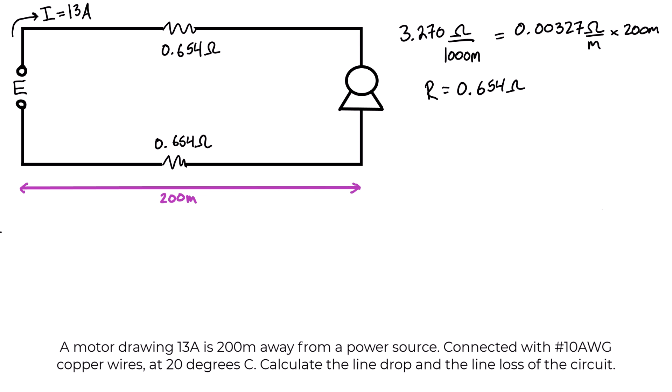If you're not given this number 3.270 ohms per thousand meters, you might be given other table values or expected to know other table values. The alternative way to get to this answer would be to know this equation where resistance equals resistivity times the length of the conductor divided by the cross-sectional area. Maybe this formula looks familiar, or maybe some of these values have been provided, or you're expected to know the resistivity of copper at 20 degrees Celsius or the cross-sectional area of certain AWG sizes.